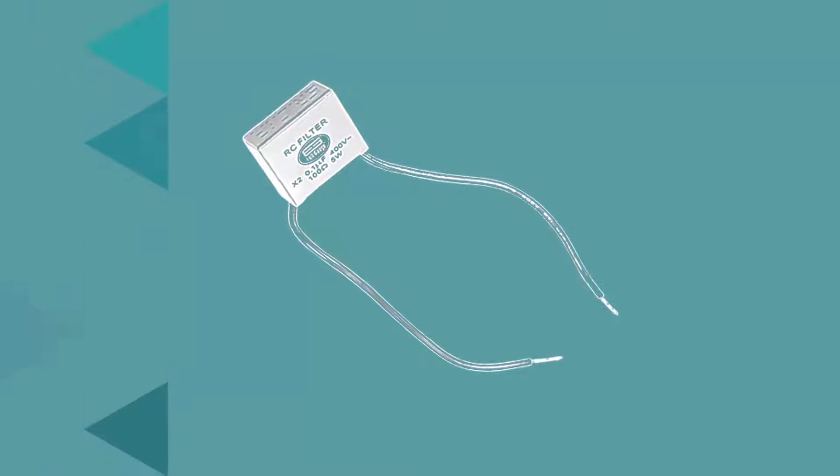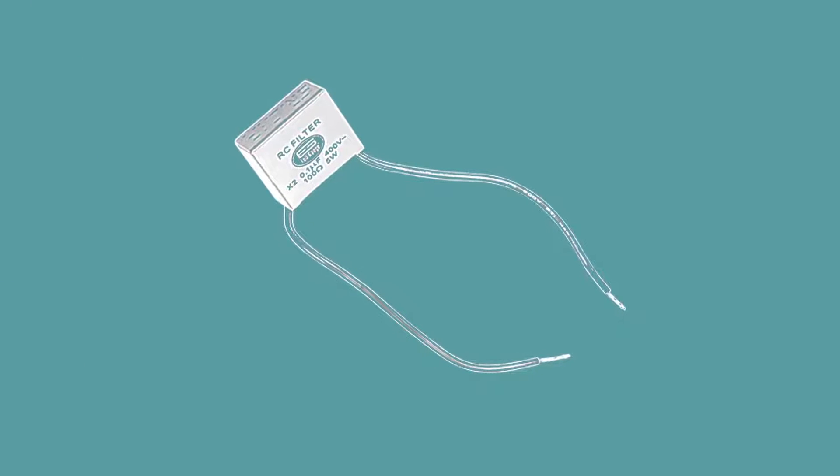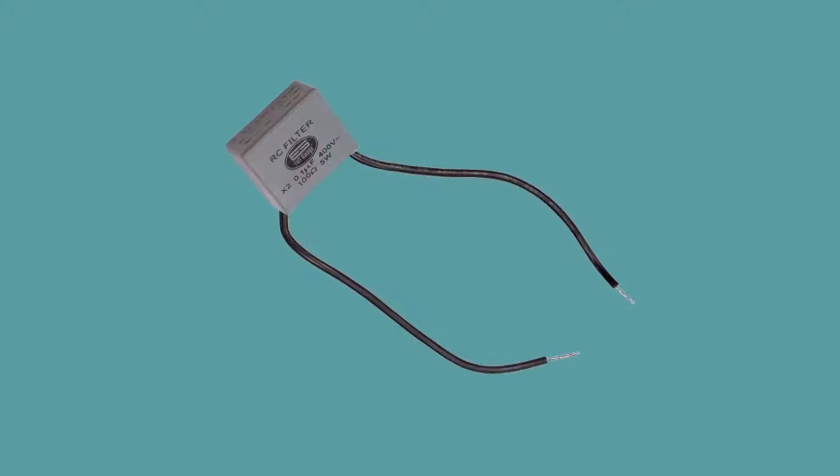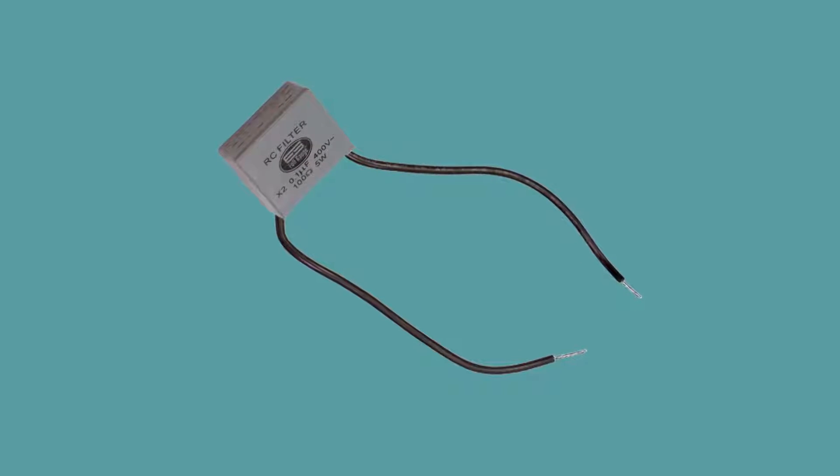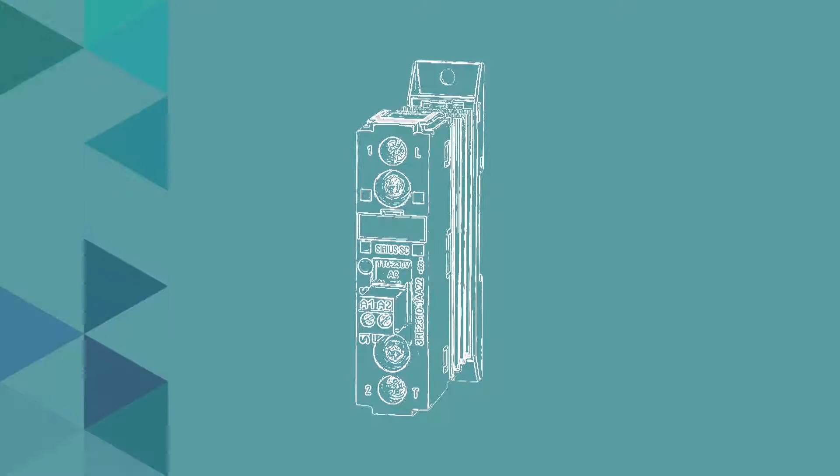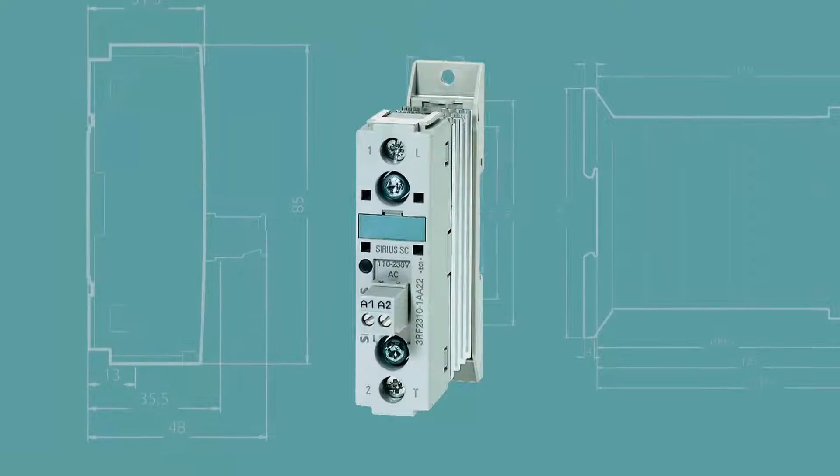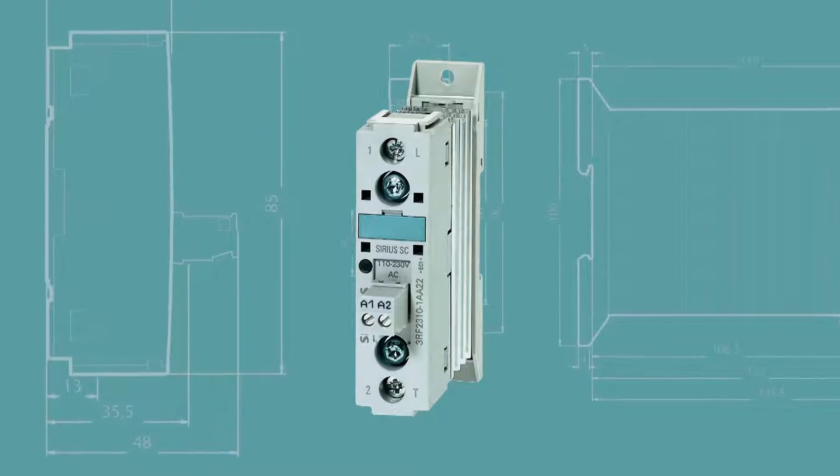Important! According to international standards, we recommend installing an RC type transient suppressor filter in all facilities, regardless of power. For loads of greater than 2 horsepower, use a contactor of suitable capacity. The RC filter and the contact switch do not come with the product.